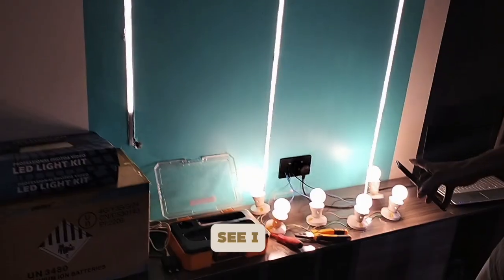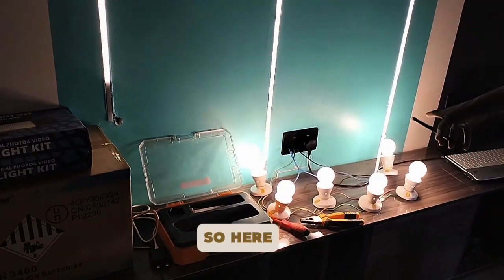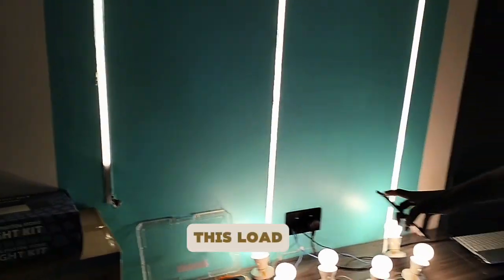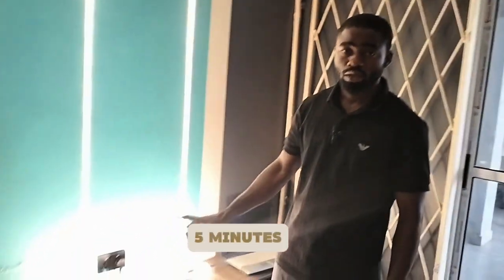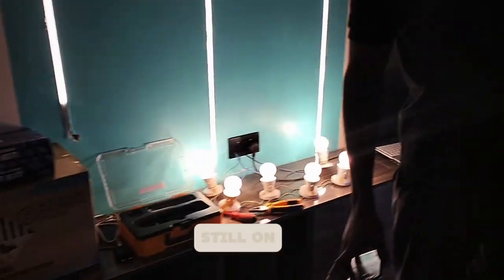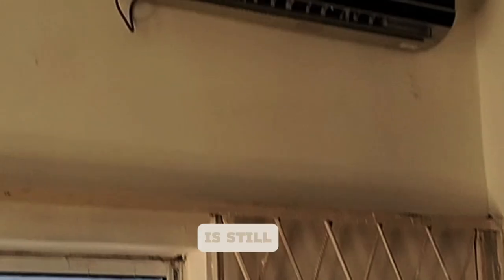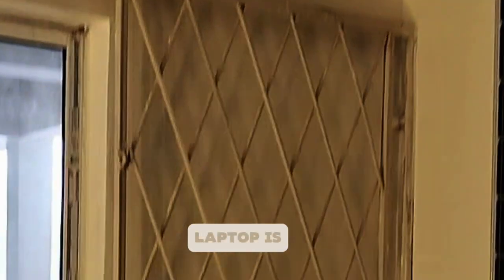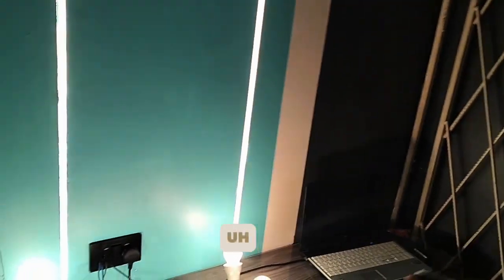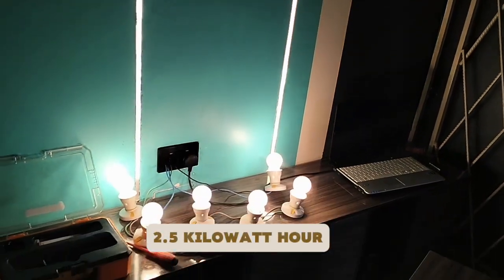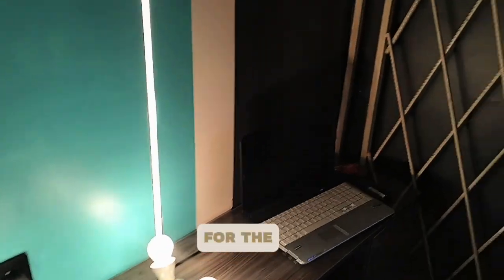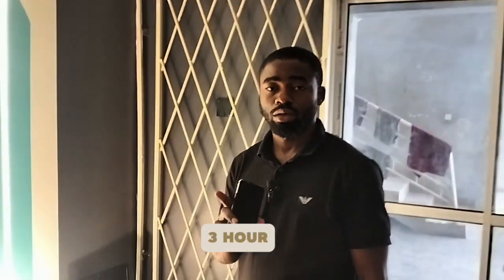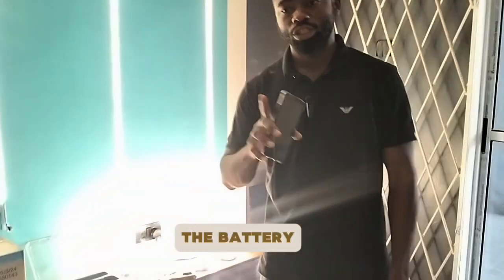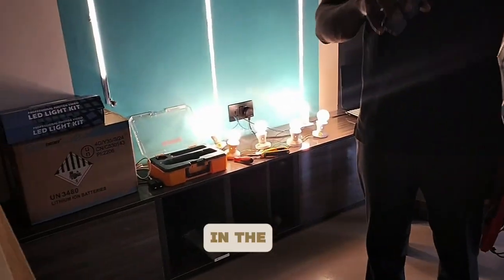And if you can see, I added another bulb to make it 6. So here we have 600 watts. We've maintained this load for the past 3 hours 5 minutes. Our AC is still on. The fan also is still running, and our laptop is still on the inverter. So we've maintained this load on that two batteries, 2.5 kilowatt hour each from Lemax, for the past 3 hours 5 minutes. So let's check out the battery, how much voltage we have left in the battery.